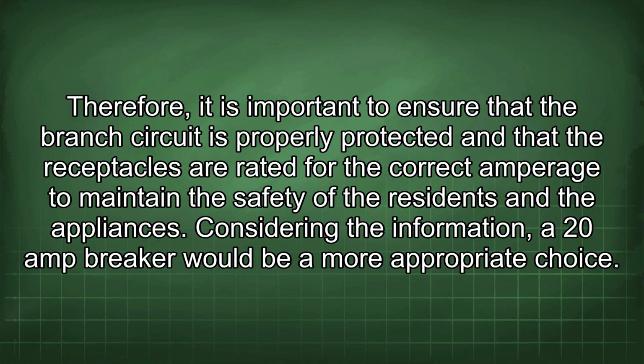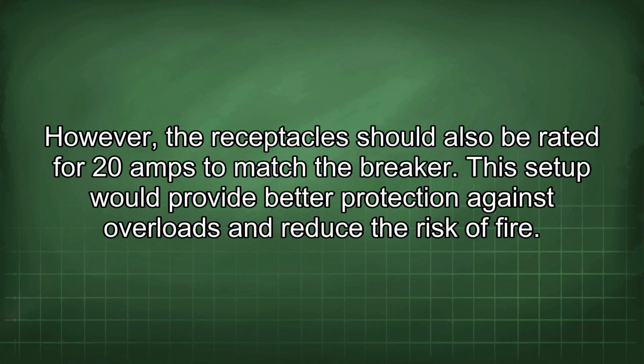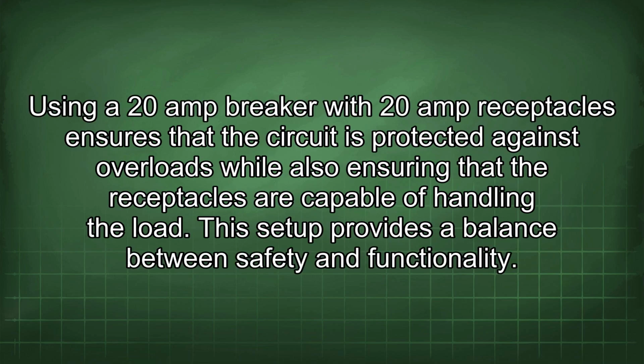Therefore, it is important to ensure that the branch circuit is properly protected and that the receptacles are rated for the correct amperage to maintain the safety of the residents and the appliances. Considering the information, a 20 amp breaker would be a more appropriate choice. However, the receptacle should also be rated for 20 amps to match the breaker. This setup would provide better protection against overloads and reduce the risk of fire. Using a 20 amp breaker with 20 amp receptacles ensures that the circuit is protected against overloads while also ensuring that the receptacles are capable of handling the load. This setup provides a balance between safety and functionality.